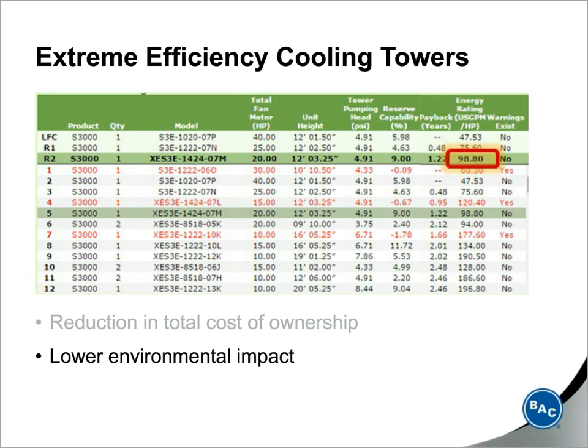It's 98.8 GPM per horsepower. Compare that to the model that has the lowest first cost, which is 47.5 GPM per horsepower. And you can see that the extreme efficiency cooling tower has twice the efficiency as the unit with the lowest first cost. Now, this energy reduction also lowers total cost of ownership, and it has a lower environmental impact since only half the energy is consumed.